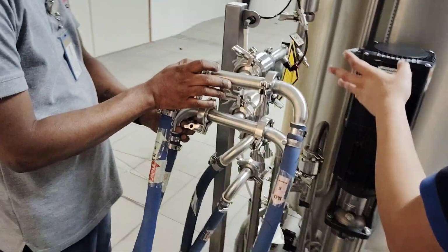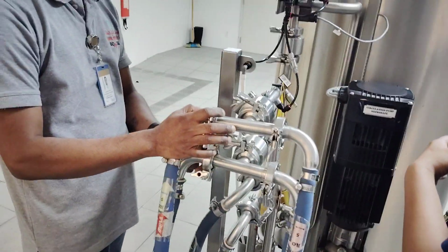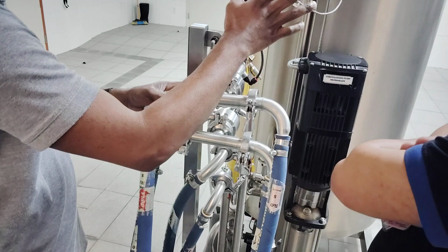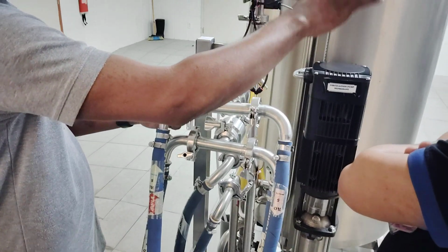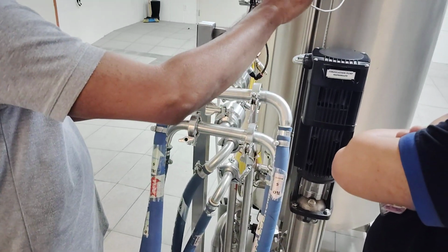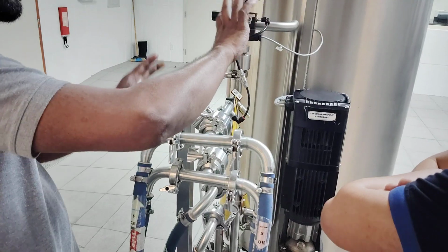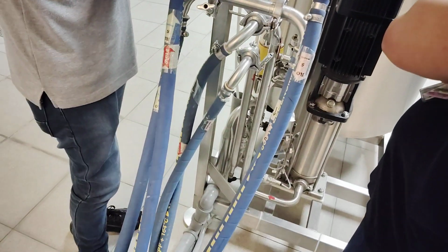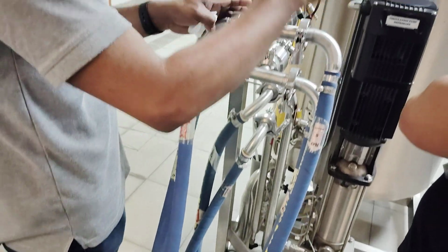So this is the last stage before it goes to the patient. This is the last area. They also have a program now. Whichever RO is running, it will automatically take the test. It's automatic. Today this RO runs, tomorrow that RO runs, it's a program. It doesn't mean this RO has to run and that one not. Any RO can be run, it's an automatic program.